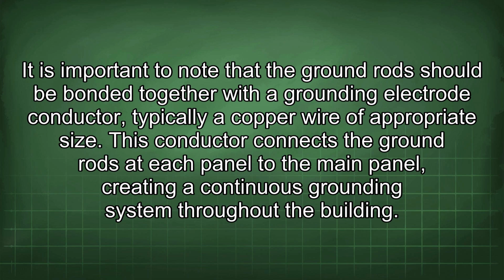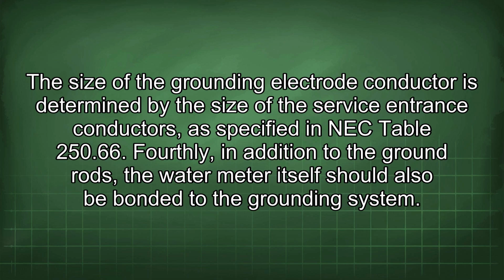This conductor connects the ground rods at each panel to the main panel, creating a continuous grounding system throughout the building. The size of the grounding electrode conductor is determined by the size of the service entrance conductors, as specified in NEC Table 250.66. Fourthly, in addition to the ground rods, the water meter itself should also be bonded to the grounding system.